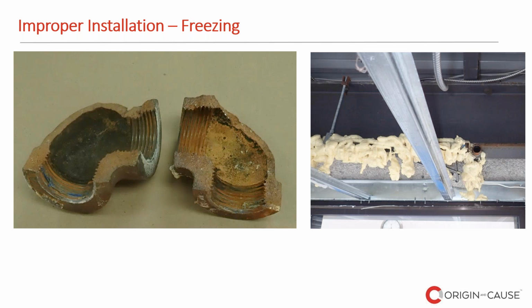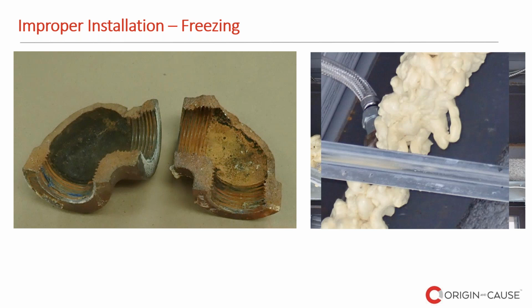Like this is a very typical failure on a steel pipe or a steel fitting. When it freezes, it splits. And you can see on the picture on the right, that's where it came from. And you can see that the insulation there was not pretty good. Actually, it's not approved insulation. Whoever was the contractor there did a really bad job. And obviously, my job was to point that out. And that was actually a very, very easy subrogation case for my client. That's the foam they used.